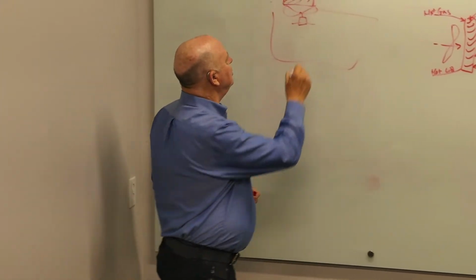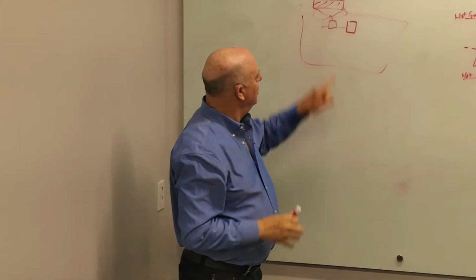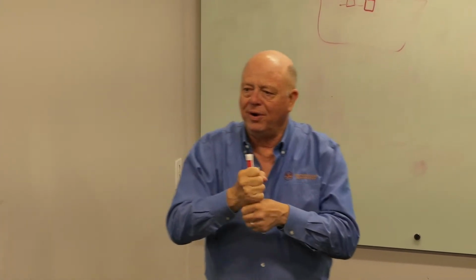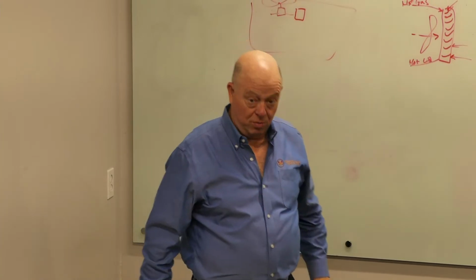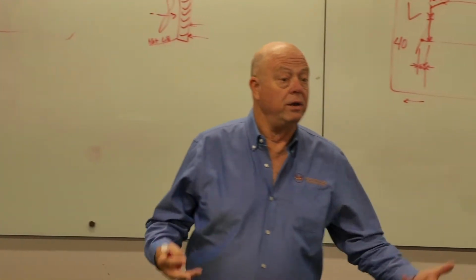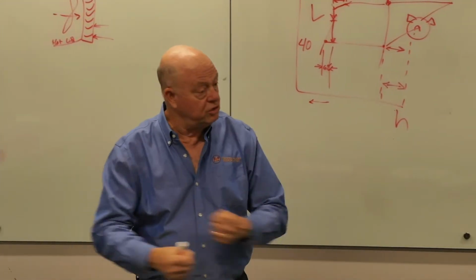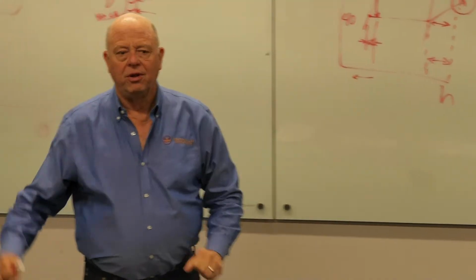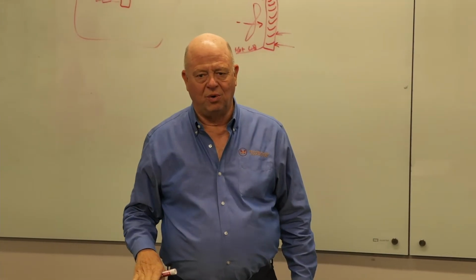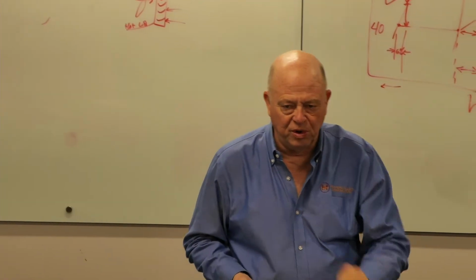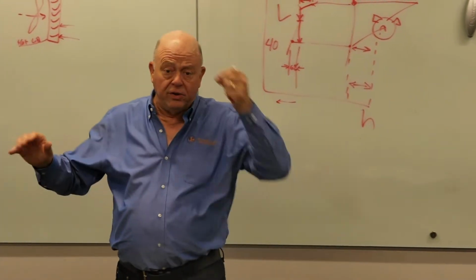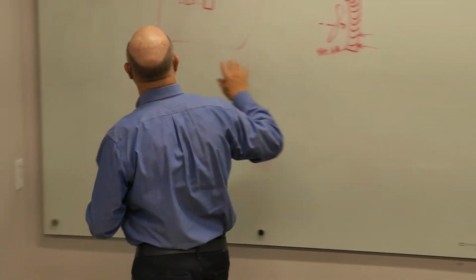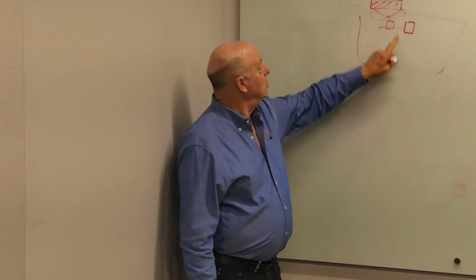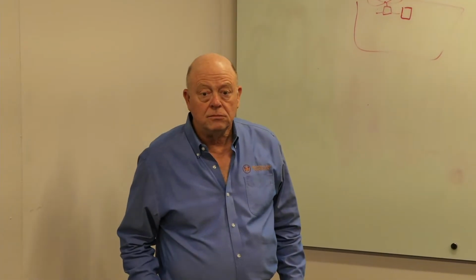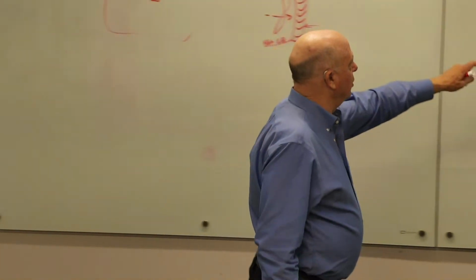Then they started offering two kinds of motor. This was the standard bearing, but you could buy that condenser fan motor with ball bearings. It was an add-on. The contractor had to swap it out in the field when they installed the unit. But if you did that, now you could take it all the way down to 0 or 10 or whatever the bottom speed that variable speed thing would do. And that's what they ended up at some point in the 80s standardizing on: if you were going to go with Motor Master, they wanted you to change it out to a ball bearing motor, and then you could go any speed you want, and it did a great job of controlling this.